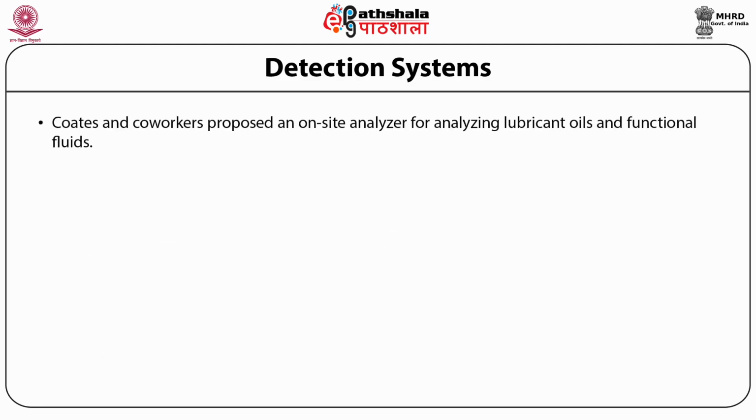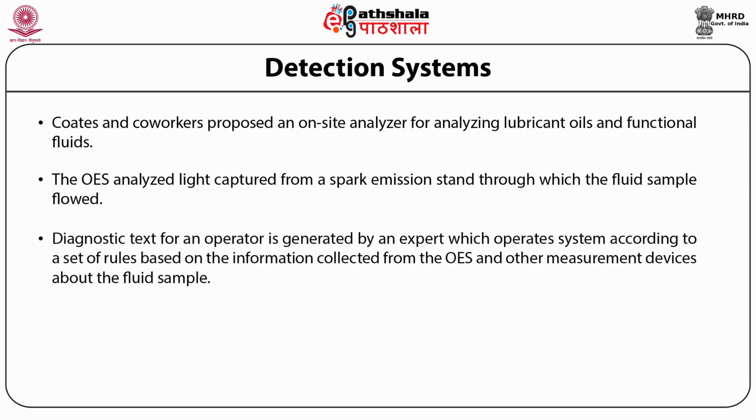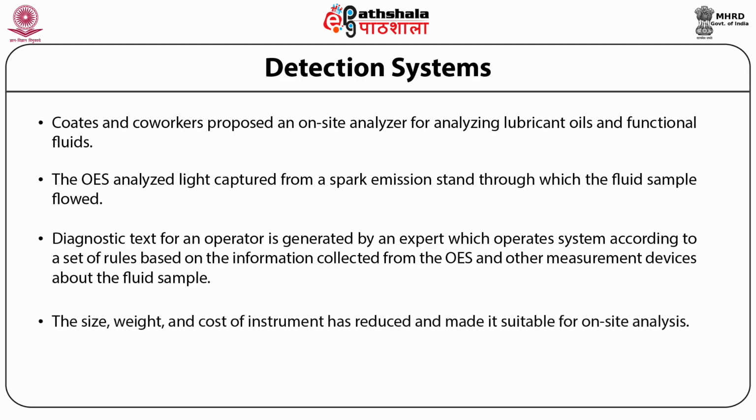Coates and co-workers proposed an on-site analyzer for analyzing lubricant oils and functional fluids. The OES analyzed light captured from a spark emission stand through which the fluid sample flowed. Diagnostic text for an operator is generated by an expert system which operates according to a set of rules based on the information collected from the OES and other measurement devices about the fluid sample. The size, weight, and cost of the instrument has reduced and made it suitable for on-site analysis.